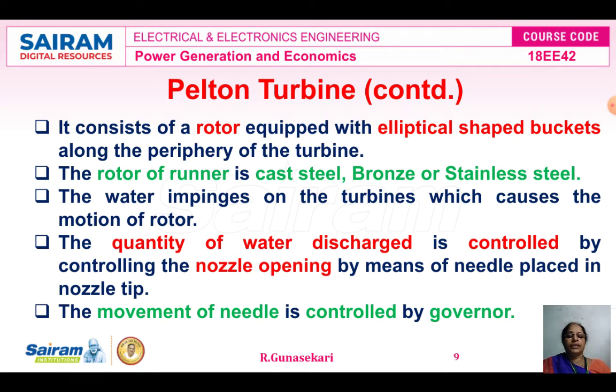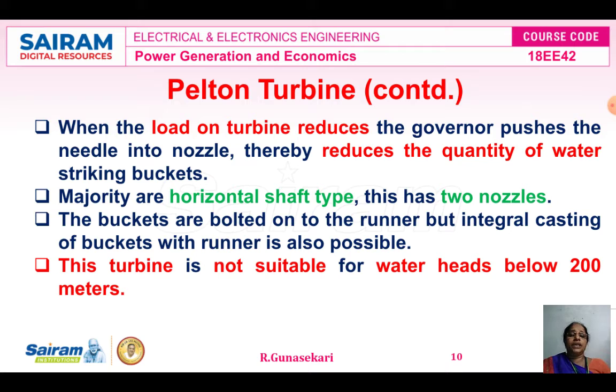The movement of the needle is controlled by the governor — the same governing principle we studied earlier. When the load on the turbine reduces, the governor pushes the needle into the nozzle, thereby reducing the quantity of water. The Pelton wheel turbine is predominantly a horizontal shaft type and has two nozzles. The elliptical-shaped buckets are bolted onto the runner, though integral casting of the buckets with the runner is also possible. The Pelton turbine is not suitable for water heads below 200 meters; it is used above 200 meters.